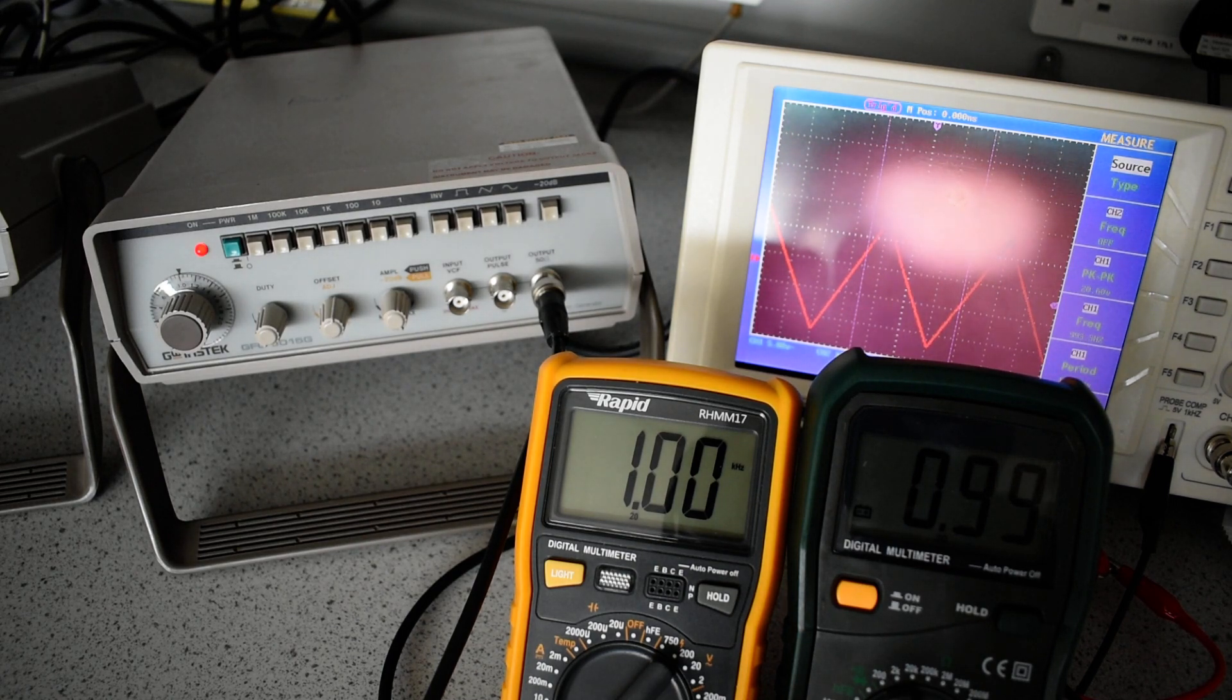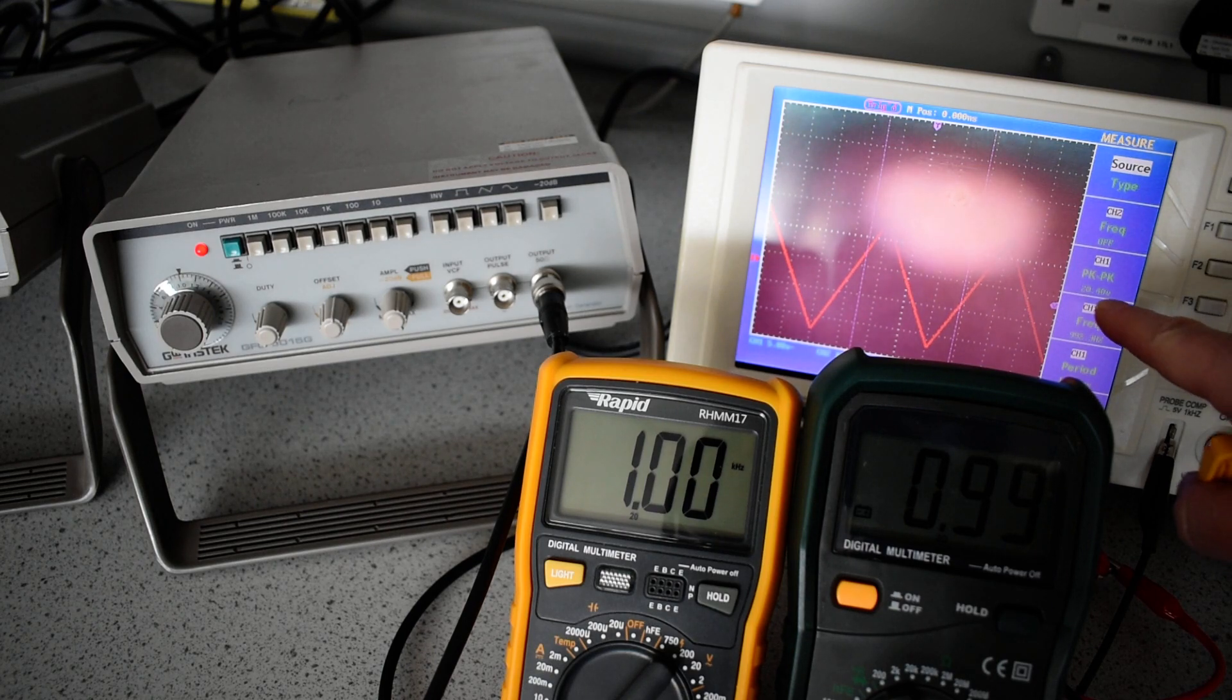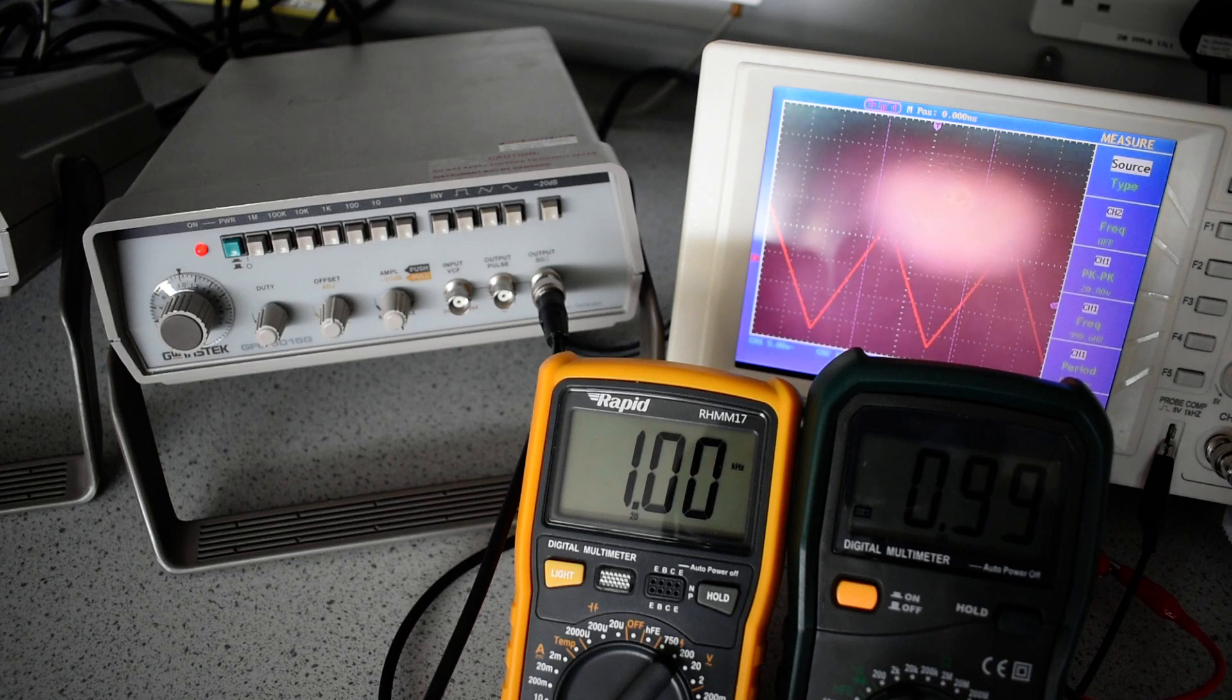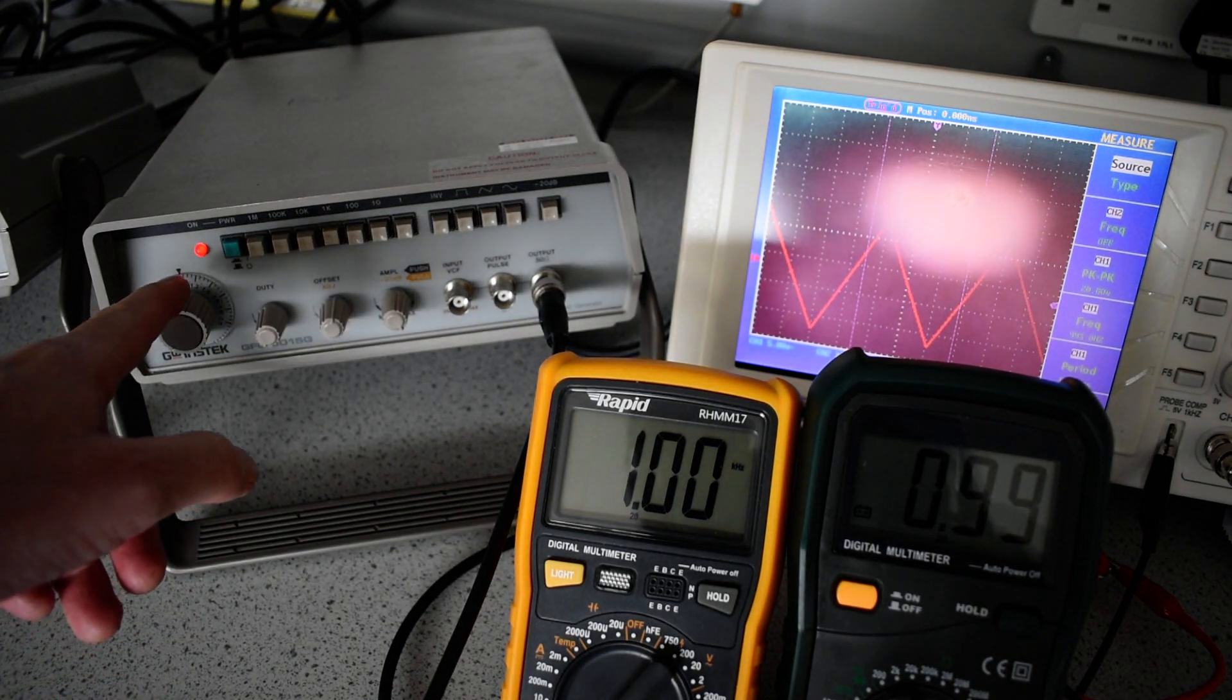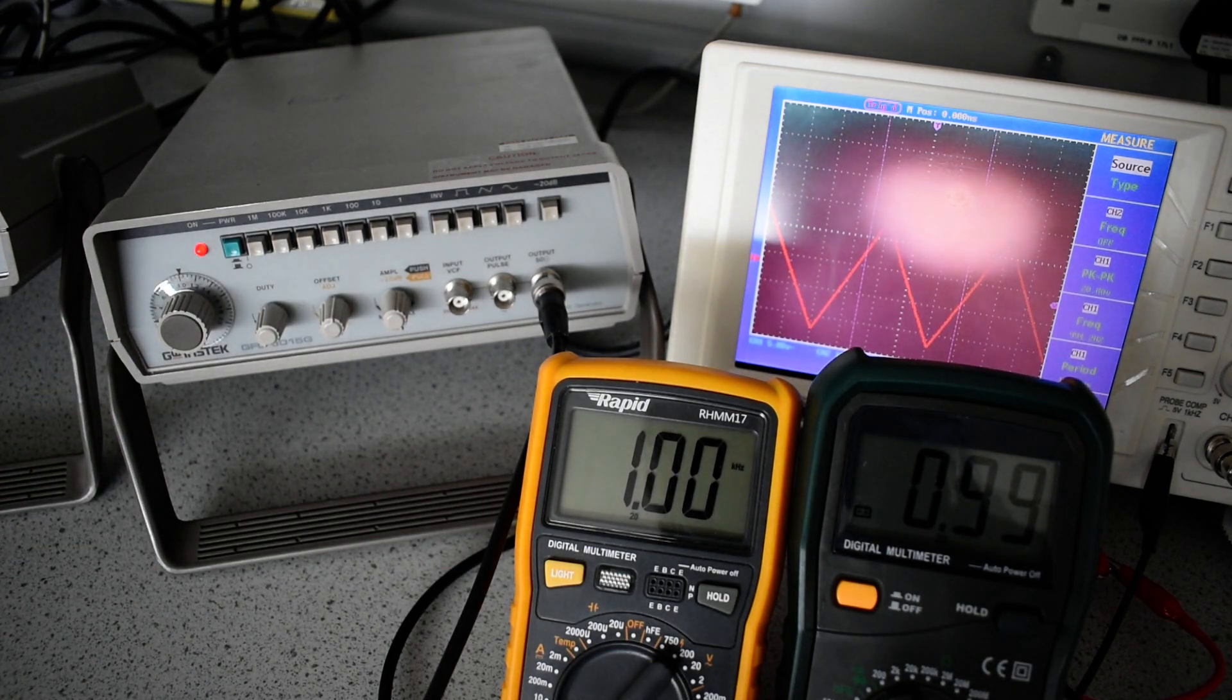It should have a peak to peak amplitude of greater than 20 volts. We're measuring 20.6, that is within spec. It should have a frequency within 5% of the dial setting, which in this case is 1000 Hz.